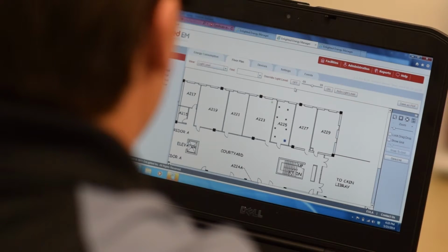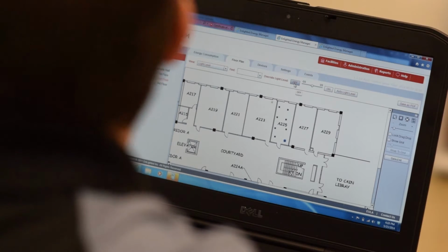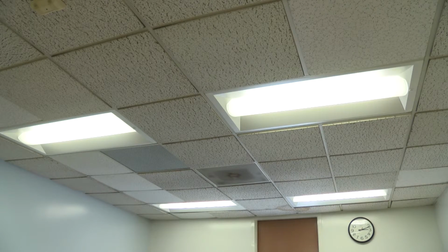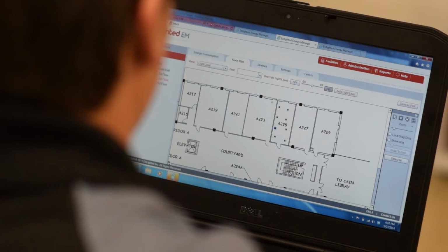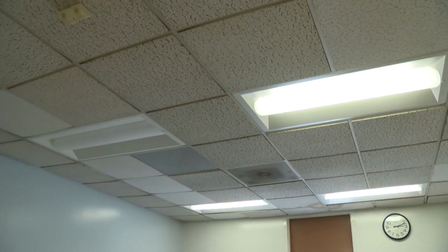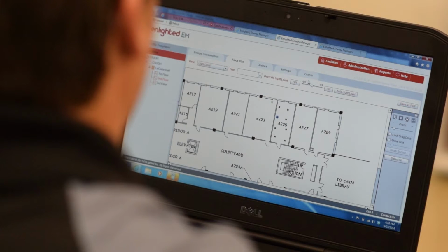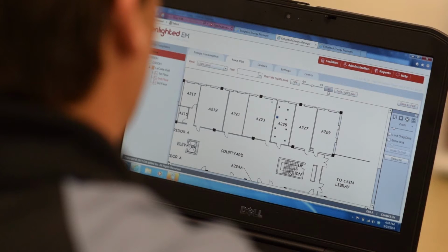In a small room like this it's just as easy as, otherwise you could exit commissioning and go back in if you selected one and use a mask. Our light went back on. We check the next one, which will be right above the chalkboard. Turn it off. It's correct. Turn it on. Do the one behind it. Off. On. Next one. Off. It's correct. On.